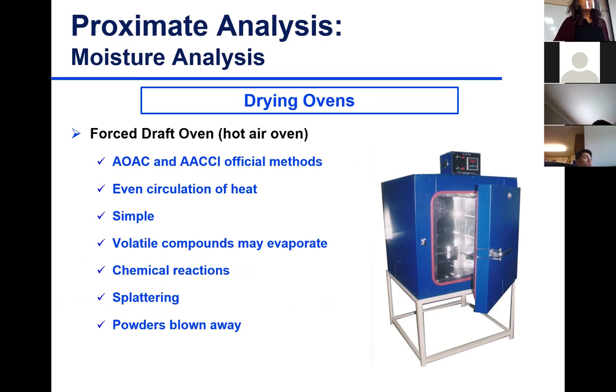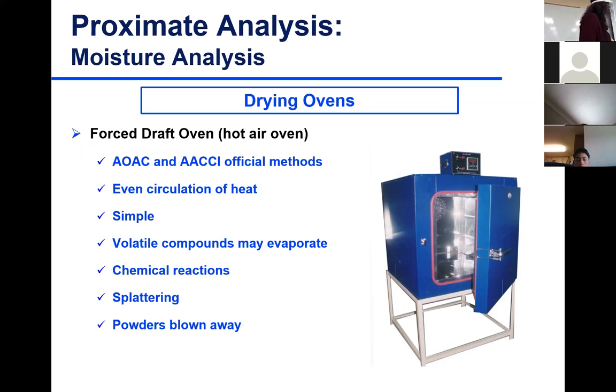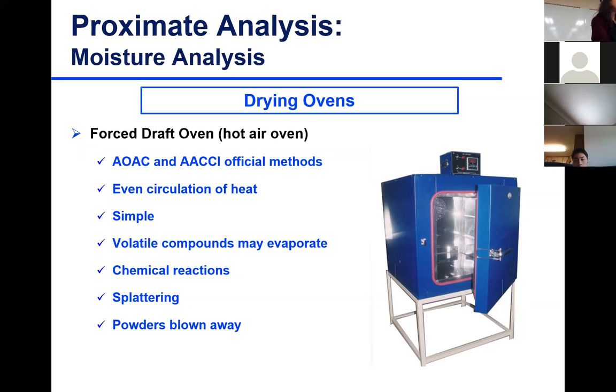It's called a forced draft oven because hot air is circulated or forced into the oven. It is an official method of analysis — you have AOAC methods and AACC International, now known as Cereals and Grains, which has official methods for utilizing the forced draft oven for many different foods. An advantage is even heat distribution, so no matter where you put your sample, you get uniform heating.